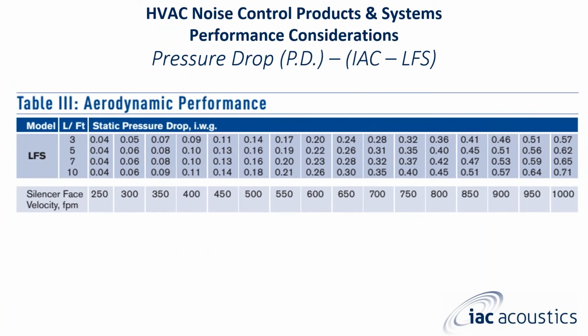We have some really unique tables within our catalog, so take a look at that at any given time. We have 3 foot, 5 foot, 7 foot, or 10 foot. What is really unique though, again, with our virtual tool, not the snap tool, but the virtual tool, you can plug in any width and height of your desire, starting at 6 inches and going on up. And you can plug in any length up to 120 inches and it will give you the pressure drop.